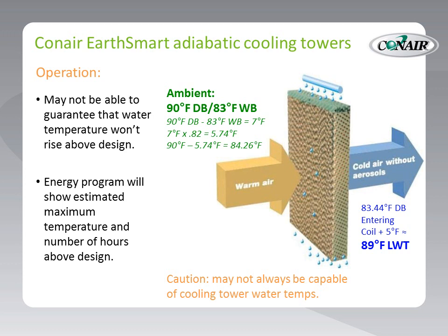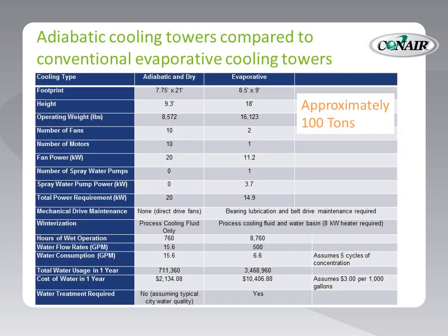In some parts of the country, ambient conditions can cause the leaving water temperature to rise above 85°F. Conair's Energy Analysis Program will provide you with an estimate of the highest possible leaving water temperature expected and, importantly, an estimate of how many hours during the year the temperature could be above this design criteria. Here is a brief comparison of a typical 100-ton traditional evaporative cooling tower and an adiabatic dry cooler used in the Chicago area.